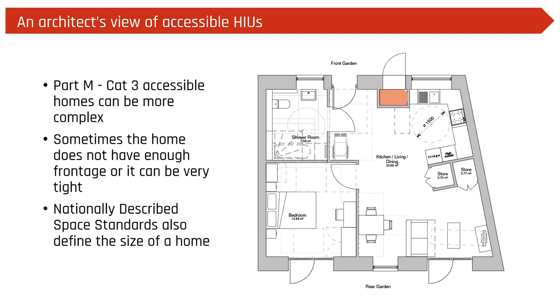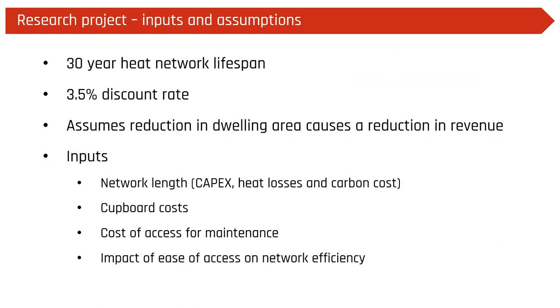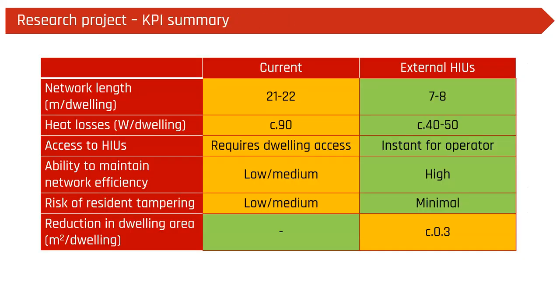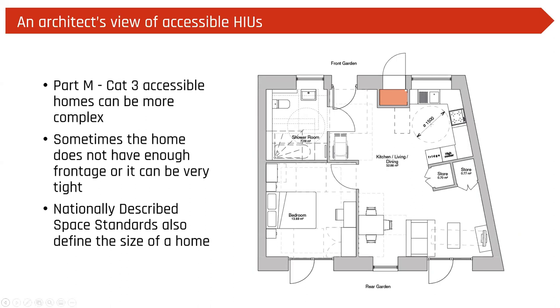And the last thing to consider with dwellings is that we're working to nationally described space standards. The government sets space standards on dwellings and their minimum sizes. So we're often pushed to work to the absolute minimums. Whilst the most obvious thing would be to increase the size of the dwelling to fit that HIU cupboard in, we can't always do that. So we are looking at stealing space from the living room, because that's the only space we're allowed to steal from. Bedrooms are set sizes, bathrooms are set sizes, kitchens are set sizes, so we can only steal out of that living space. But back over to Tom. That's all for me.